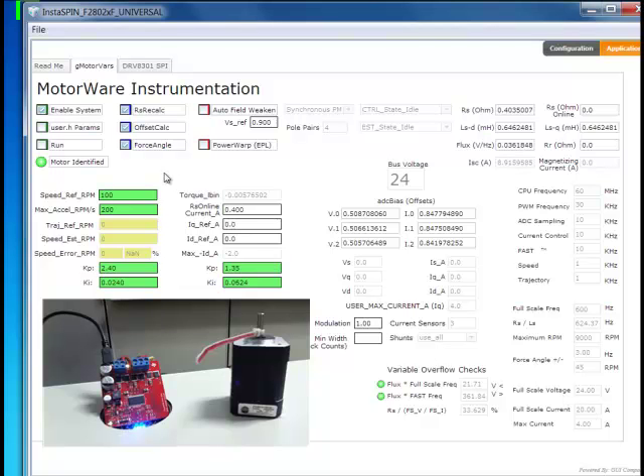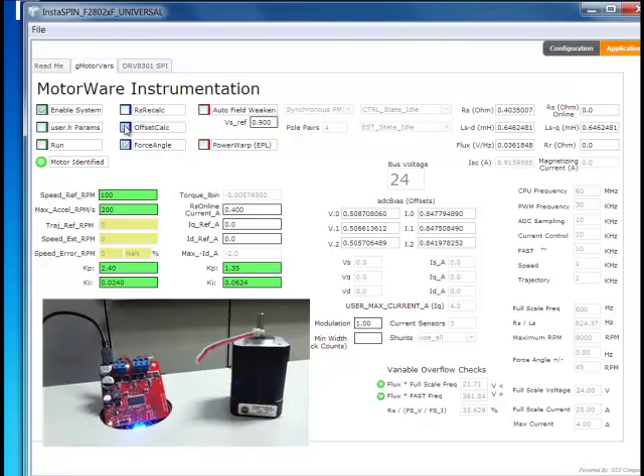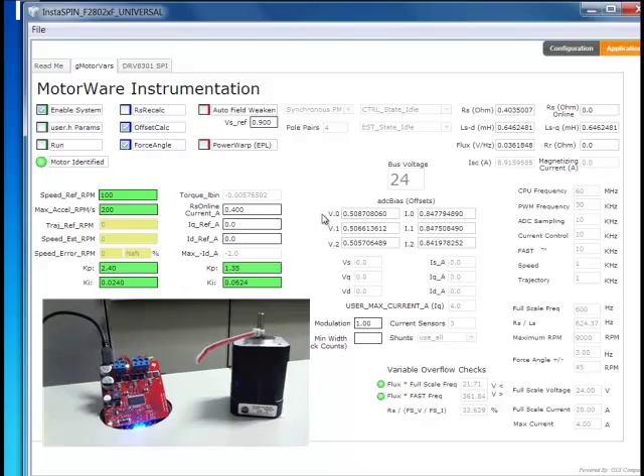So the next thing I like to do is to go ahead and start the motor, just to make sure that it identified correctly and it seems like it's running pretty well. So in this case, I'll turn off my resistance calculation. I will leave my offset calculation on. Because I have not saved these values, I want it to do an offset again before it starts.